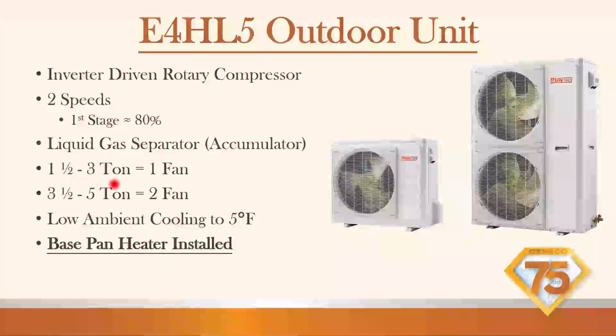Liquid gas separator, 1 to 3 ton, 1 fan. It's got accumulator, low ambient cooling down to 5 degrees. We do lose capacity, but you don't need a low ambient kit if you're running this for cooling. It does have a base pan heater installed. So for defrost, it'll melt any ice buildup on the bottom of that unit.